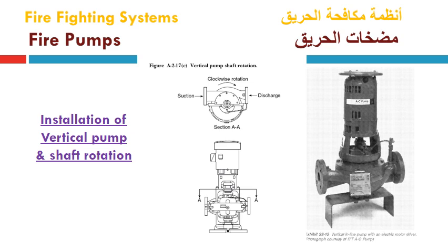This slide shows how the vertical pump is installed in different operations, especially the inline pump, and the relationship between the shaft and the pump. The shaft is located vertically and the impeller is affixed horizontally, with the suction flange and the discharge flange. The flow comes in and goes to the impeller eye, and is collected according to the rotational motion in this volute casing until it reaches the discharge flange.